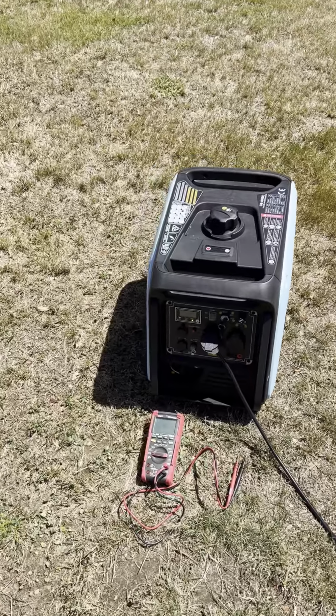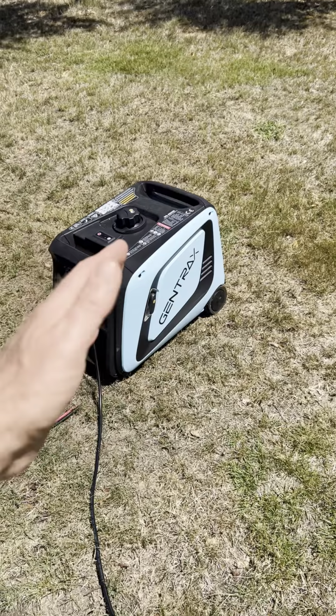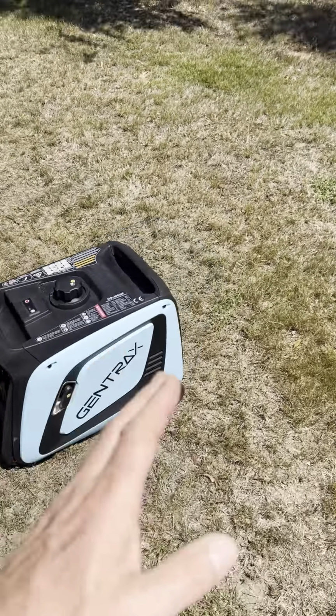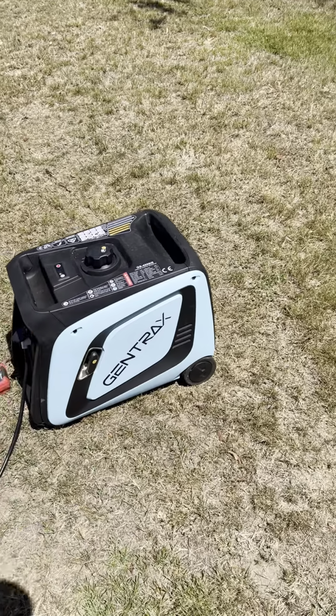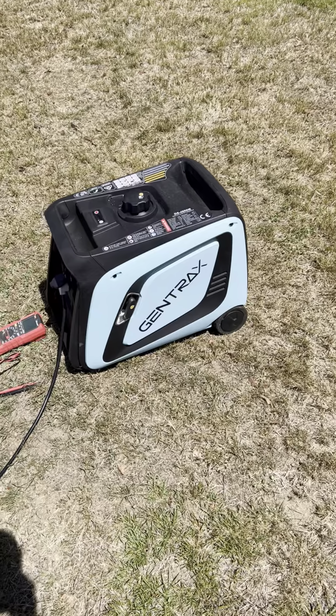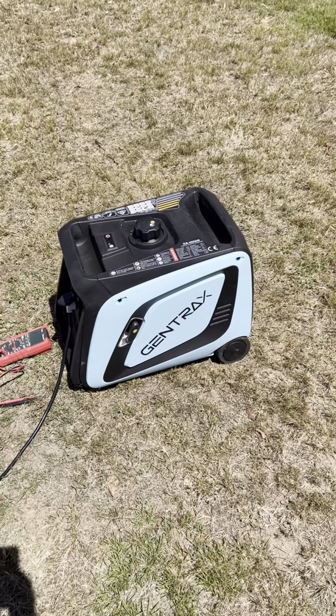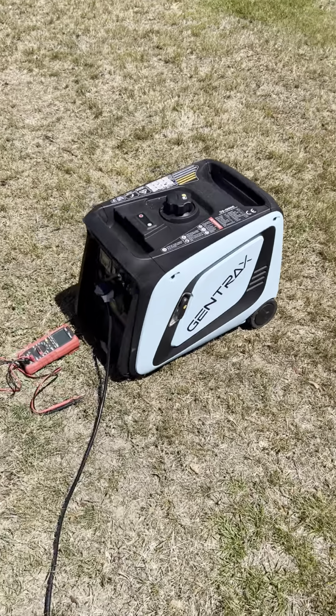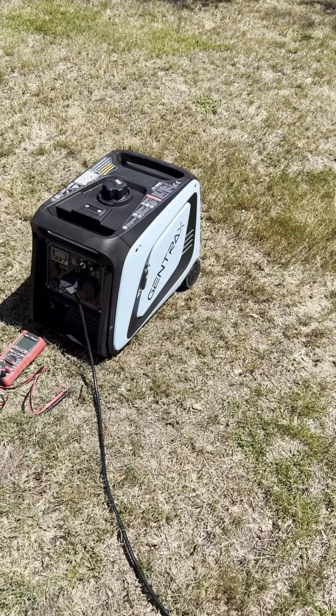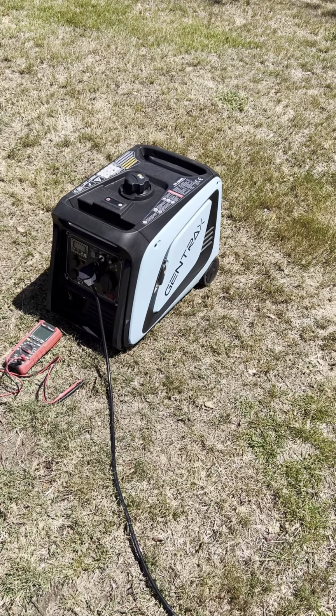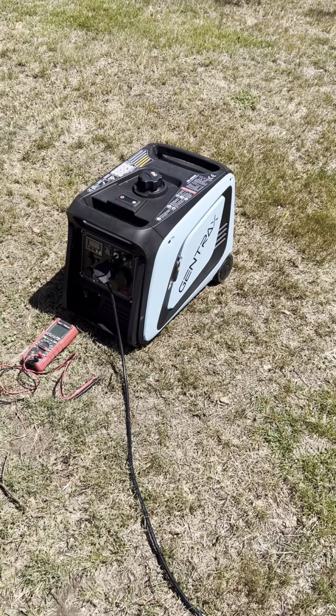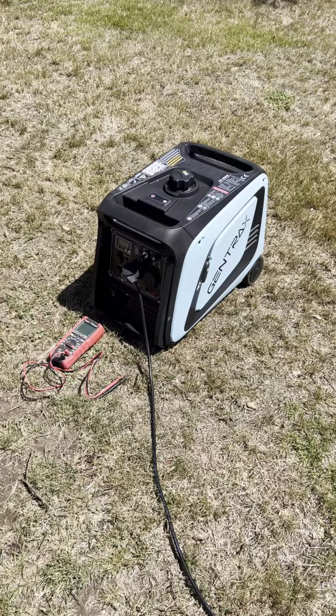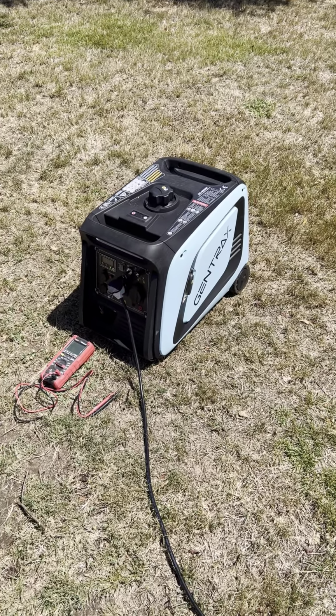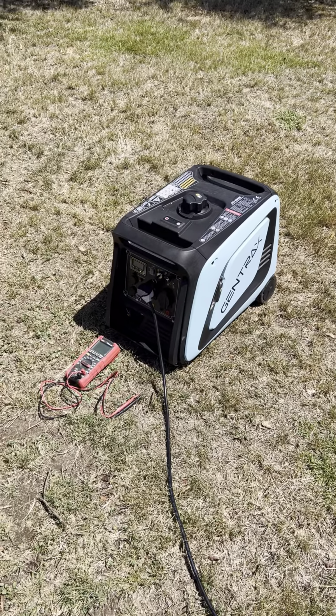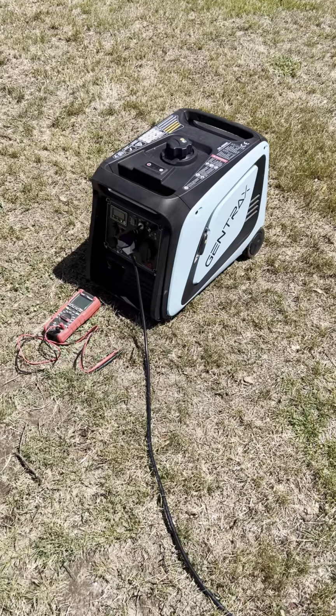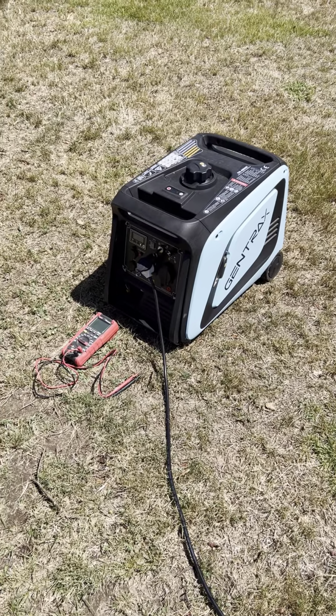Now this is where it gets a bit funny. Remember it's rated 3.5 kVA, 3.5 kilowatt full load, 4.2 kilowatt max, but I cannot start a 3/4, 750 watt compressor with head pressure relief on it. It doesn't like power tools. It won't start a 2000 watt pressure washer. It just folds back on voltage, and if you let it go long enough it'll probably end up destroying it - eventually the fault comes up on the machine. So if you want to use one of these for motor starting, unless it's got a ramp in it with an inverter, forget it. They don't do it. We put them at the bottom of the tree as far as that goes.